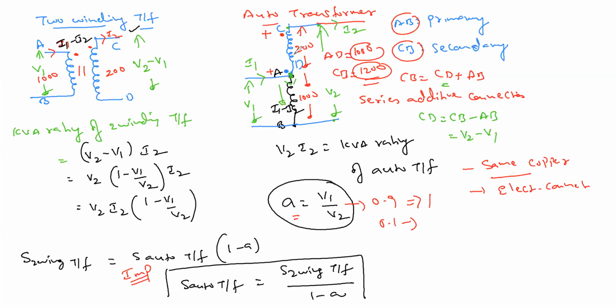समझ गए? So what is the advantage of auto transformer? With the same amount of copper, the rating of auto transformer has increased drastically here. And another point is efficiency of auto transformer is very much higher compared to the two winding transformer. Two winding transformer की efficiency is around 96 or 97, but the auto transformer efficiency होगा around 99.9 or 99%, because the losses are same here.